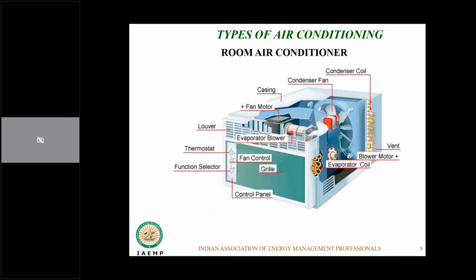Okay. So this vapor compression system has multiple ways of being used. All these 4 components are there in your window air conditioner, where you have an evaporator on the cooling side, on the room side, and a condenser on the outdoor side. You have a condenser fan, which sucks the air in through louvers on the side, passes it over the condenser coil, and then discharges the hot air out, which cools your refrigerant.